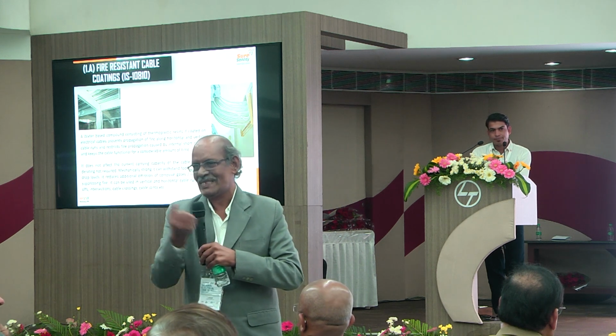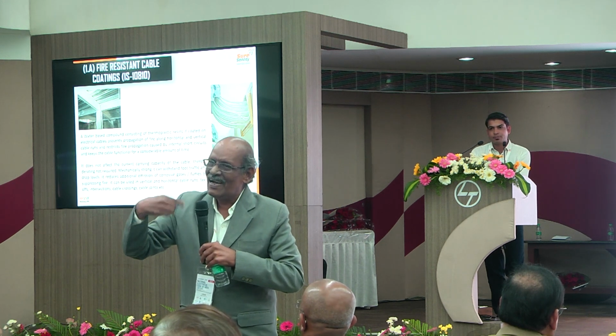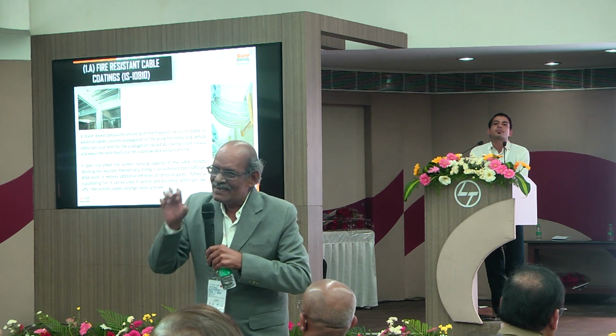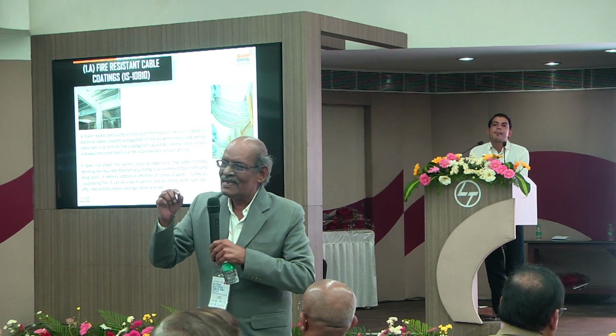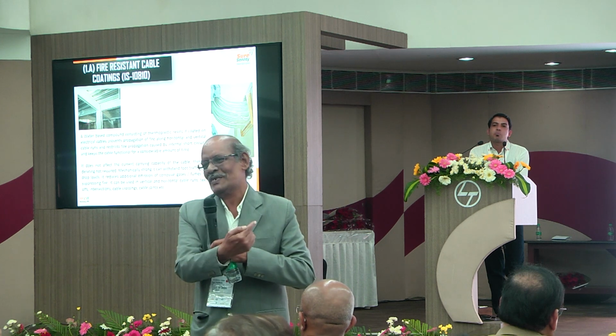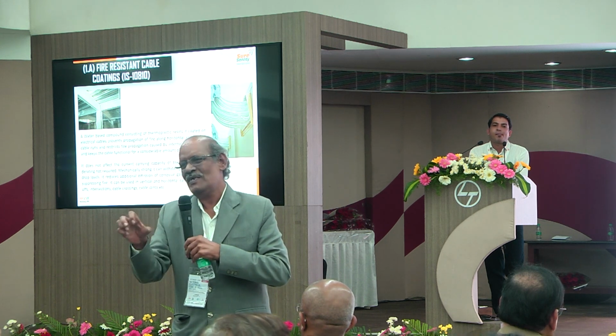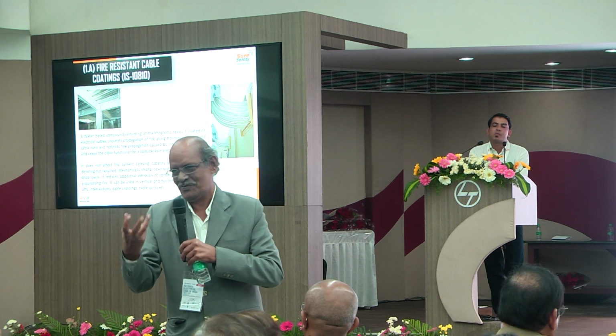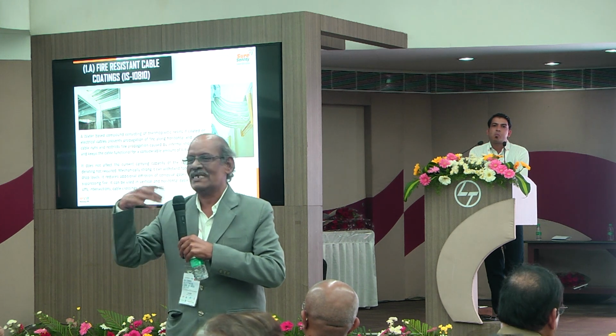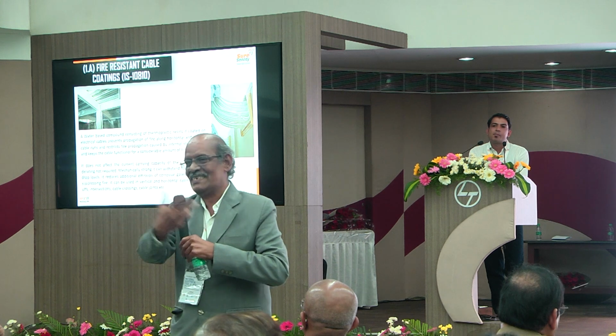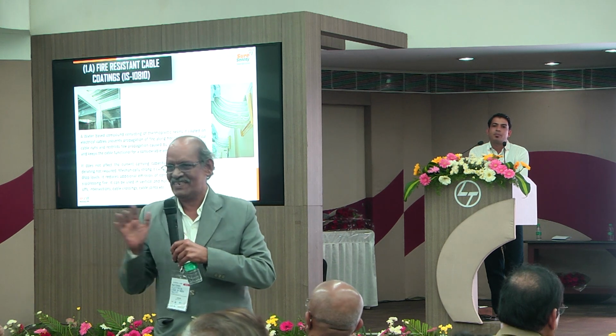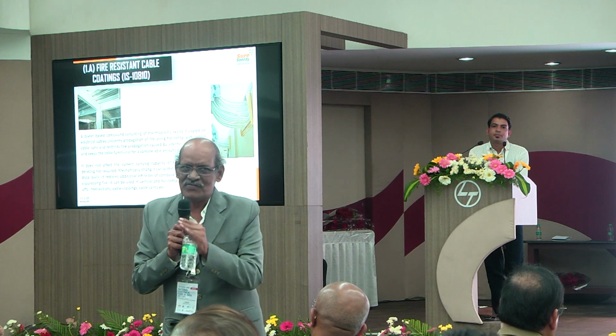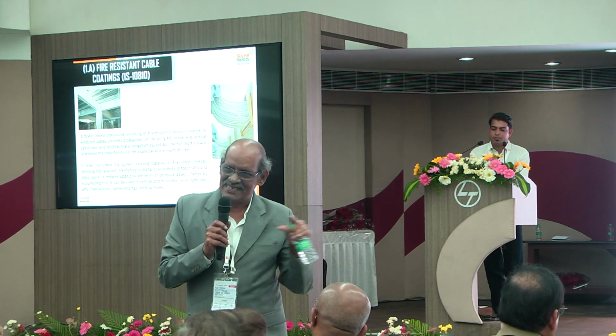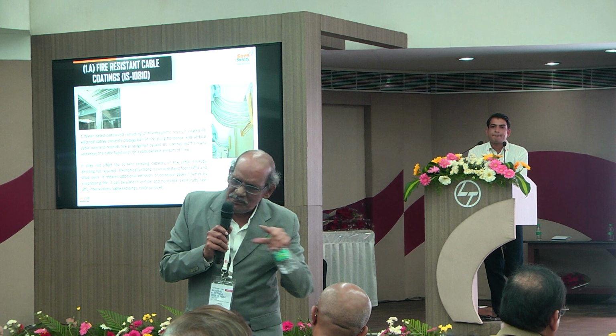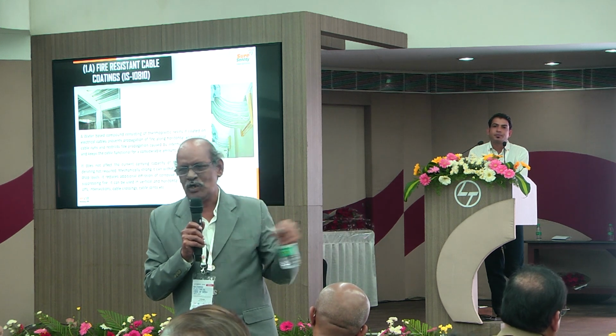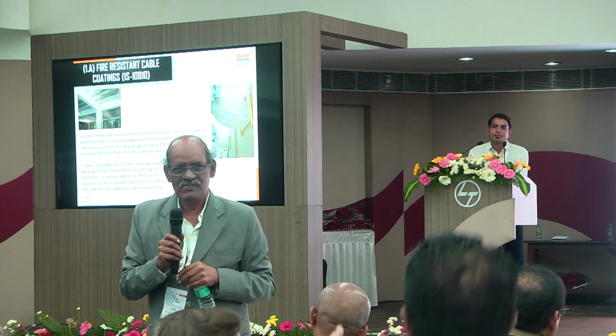It is advisable to coat the cable. As he said, it is not based on the inner material, which depends on the normal or short circuit temperature. It is not about the cable's short circuit or withstanding capacity for the fire. It is for the cable to withstand the fire from an external source to minimize aggravation. So after the fire stop, it is coated for a certain distance to limit the fire hazard. It should not go away and propagate the fire. That is my understanding.